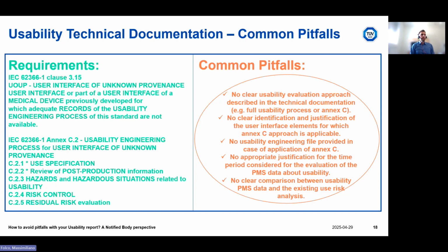No appropriate justification for the time period considered for the evaluation of the PMS data about usability. As I've said, there is no specific requirement, but the manufacturer has to select an appropriate time period. Of course, if the device has been on the market for 15 years, choosing only 1 year is not sufficient. So there should be an appropriate time period to be checked for PMS data about usability. No clear comparison between usability PMS data and the existing use risk analysis. So there should be clear criteria for comparing the PMS data and the data coming from the field about usability and the existing use risk analysis.